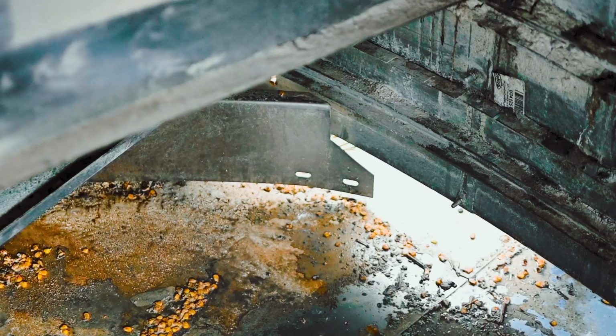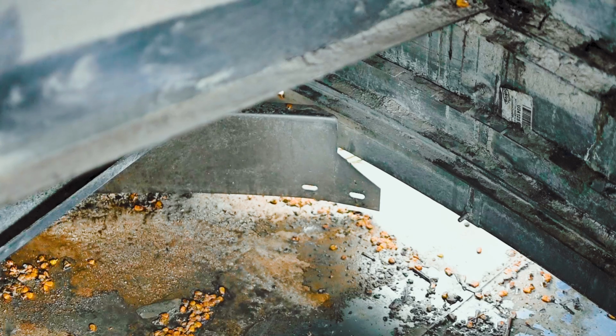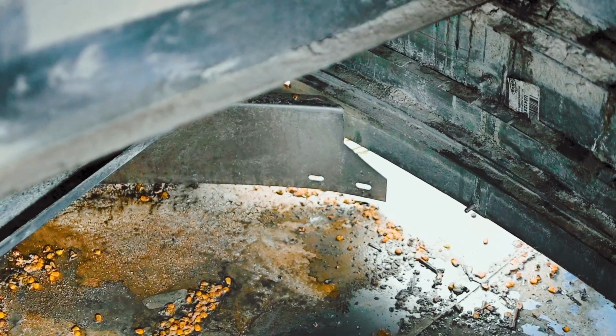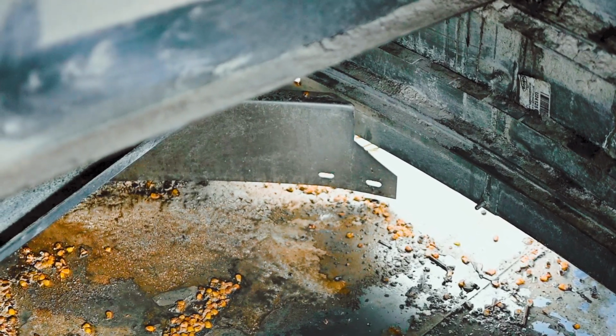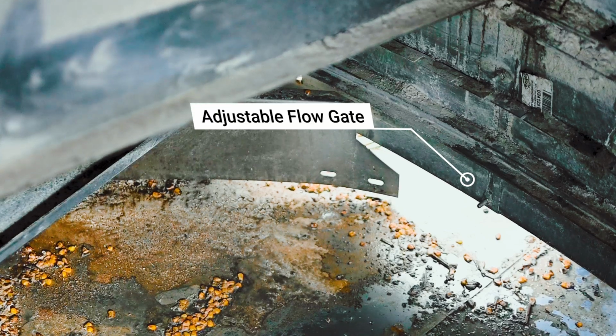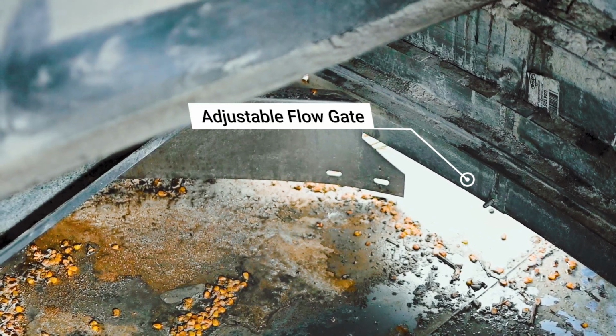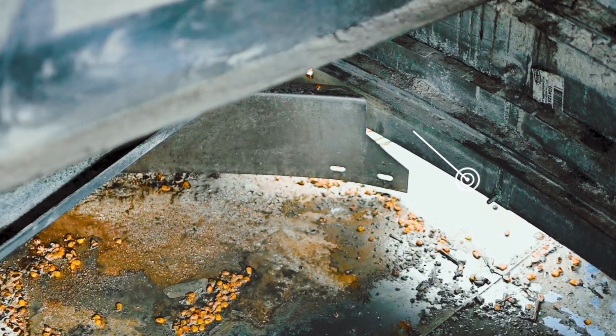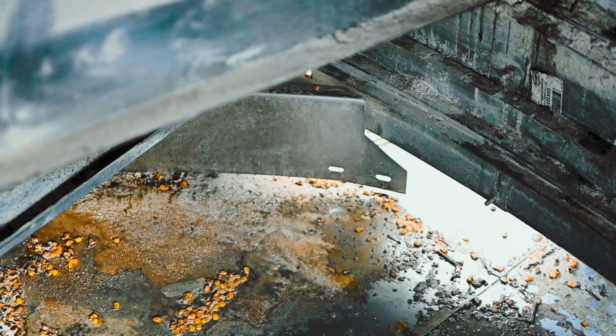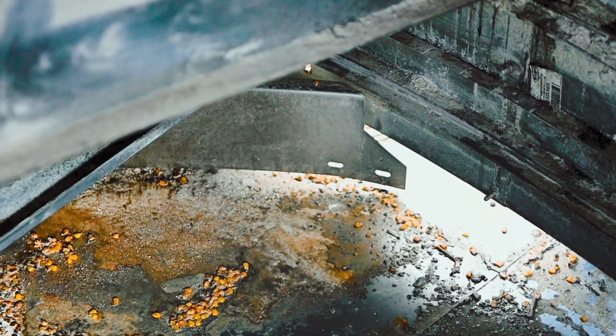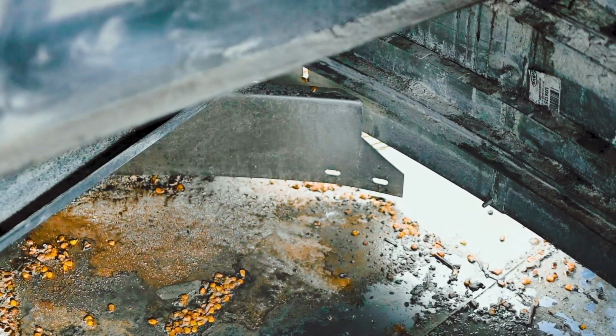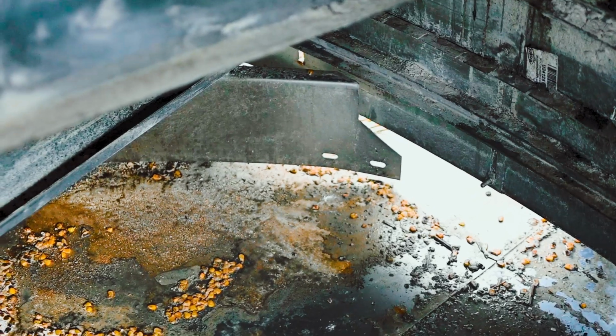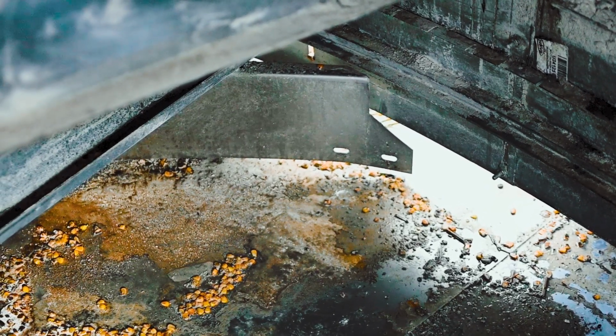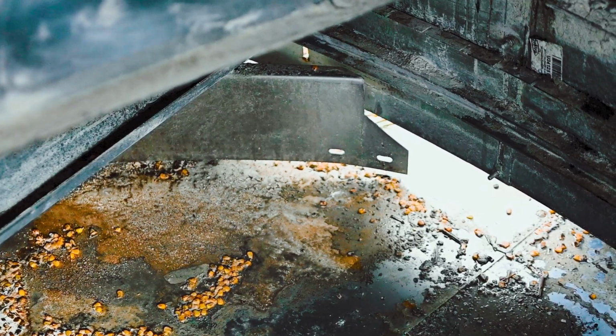Okay, this is the unload rotor area of the dryer, and this is where grain spills out from the grain columns into the unload chamber. And there are adjustable gates up here that control how much grain is allowed to flow onto the floor or onto the table. And then as the rotor turns, what we want to make sure is the rotor sweep arms are full of grain, not just boiling over the top, because that will usually cause too many amps and the motor to trip. We want to get the right amount of grain in there, and sometimes you have to adjust the flow gates up or down.